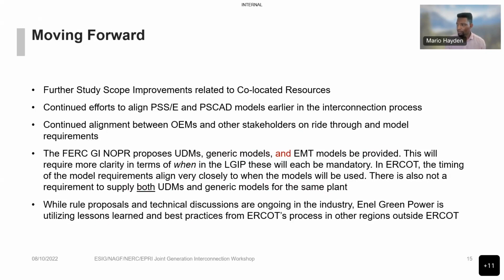Continued alignment with the OEMs and other stakeholders for ride-through requirements and model requirements. An item mentioned earlier that I think is very important is where the NOPR signifies that UDMs, generic models, and EMT models are to be provided. I think there's a need for more clarity about when in the LGIP these would be mandatory. As mentioned earlier, in ERCOT the timing of these model requirements aligns much closer to when the models will actually be used, and there's not a requirement to supply both UDMs and generic models for the same plant.